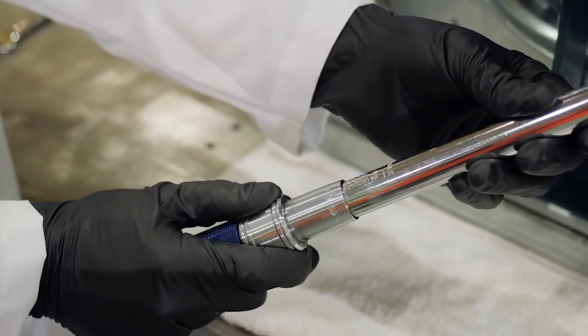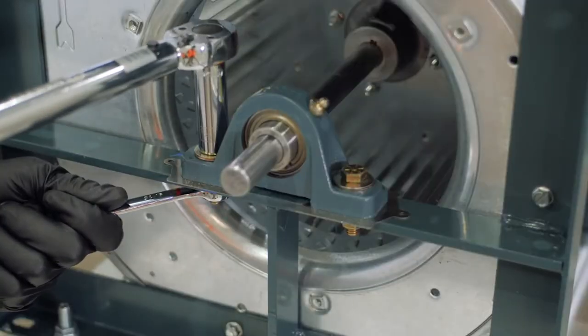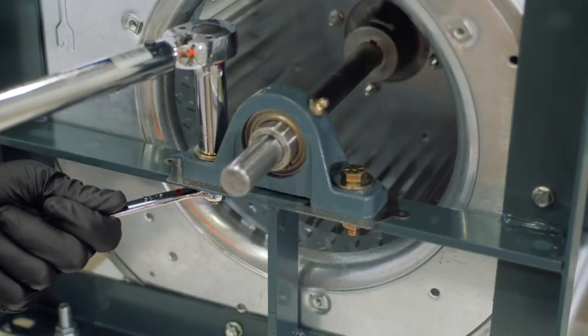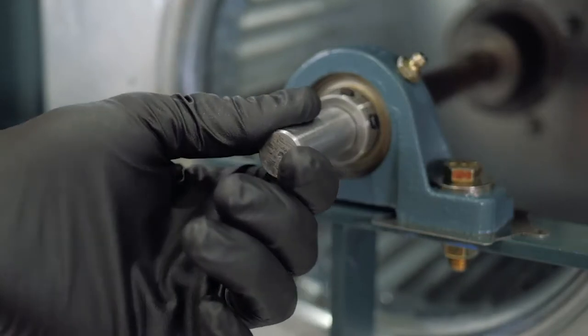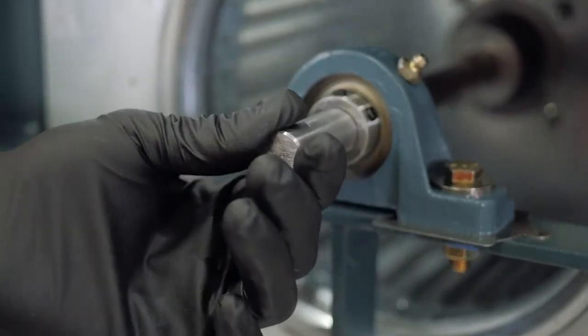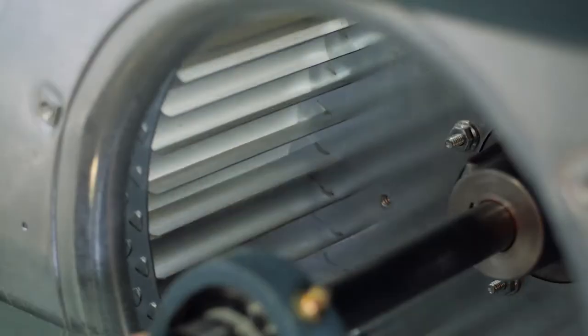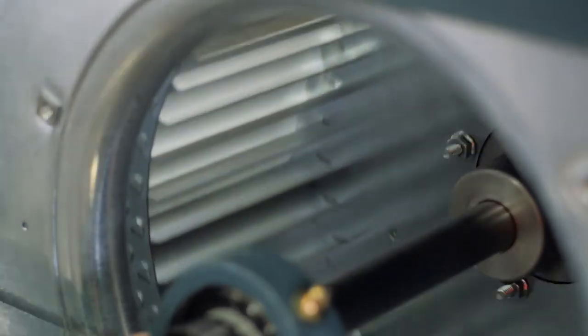Using a torque wrench, tighten the mounting bolts to the torque specification as shown in the instruction manual. Turn the shaft again by hand. If the resistance has noticeably increased, it could be an indication of an uneven mounting surface. If this occurs, remove the bearing and ensure the mounting surface is flat.